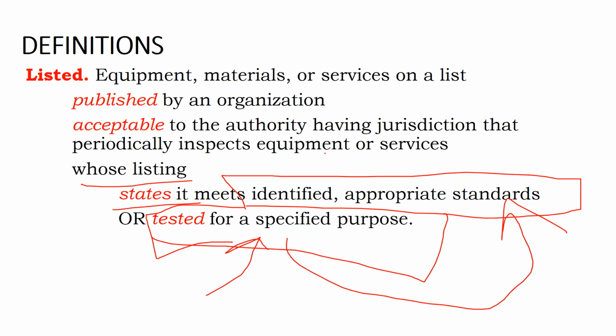The most important thing to think about is that when you're using a product, it needs to be intended for its use. And when you're thinking about, can I just go to Home Depot and pick out any wire and wire it up to my solar array? The answer is you can, as long as that cable is listed for use. If it's listed for a high temperature, environmentally resistant, direct sunlight exposure, in a wet environment, then yeah, you can use that cable up on the rooftop.